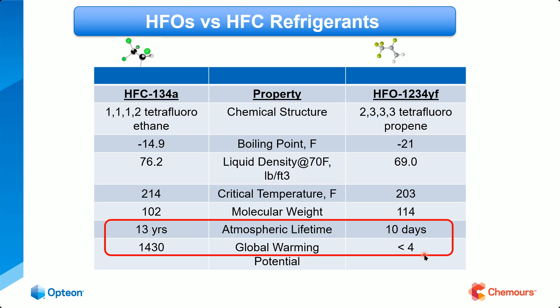What are we really saying? 134A stays in the atmosphere for approximately 13 years, while 1234YF stays in the atmosphere for approximately 10 days. That's why we're having this conversation. GWP of 1430 versus a GWP of either 1 or 4 or less, depending on what chart you're using, whether it's a 100-year chart, a 20-year chart, or whatever—because they're all numbered differently.